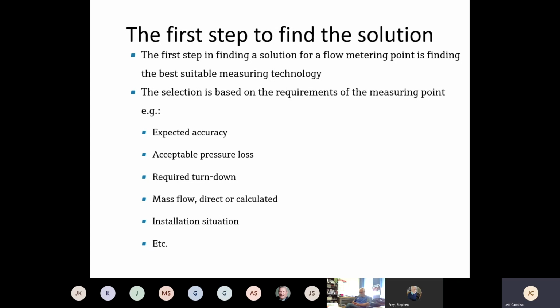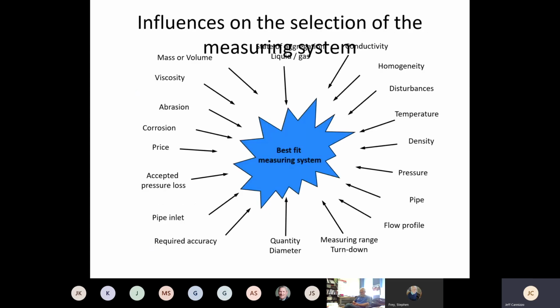What's your installation situation? And this can be multifaceted. If it's a pipe, what's your line size? Is it an 18-inch pipe, or is it a 2-inch pipe? Do you have straight run? Do you have valves and pumps in the line that you have to be aware of? Other installations like temperature probes, pressure probes, etc. And when we talk about etc., there's lots of etc. So when you talk to your sales engineer, your application engineer about selecting a flow meter, it's stressful, because the first thing he's going to do or she's going to do is come back and ask you lots of questions, because we need to look at many things to pick the best fit.